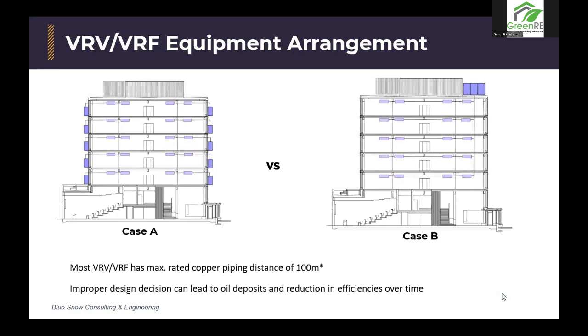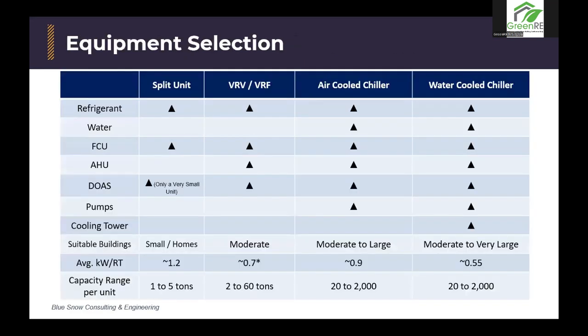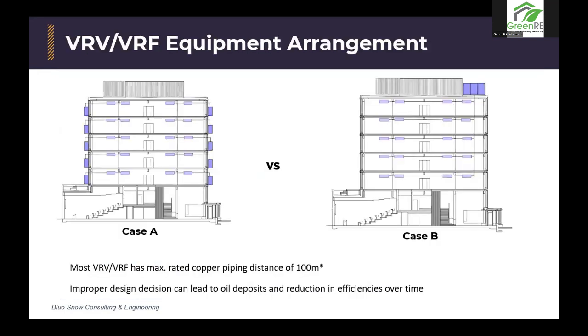Okay, now we'll be looking at the design protocols and the design philosophies and how to do certain systems. Let me just go back a bit. Just take note, in the efficiency rating, there's an asterisk towards the VRF and VRV. And in Cambodia, chilled water systems are still considered a bit rare. They do use a lot of VRV and VRF. So in our experience in dealing with VRV and VRF systems, how you design this, how you place your systems and how you run your copper, bringing in those refrigerants to your indoor unit, will play a part in how long your system maintains its efficiency.